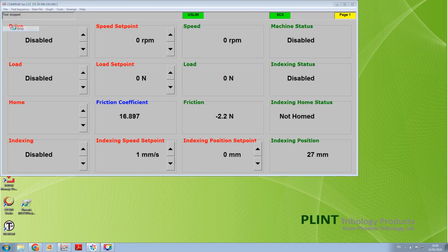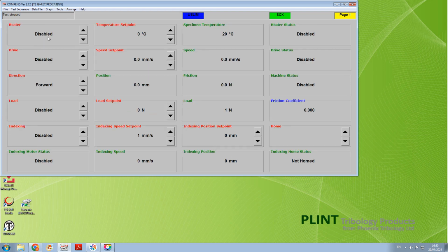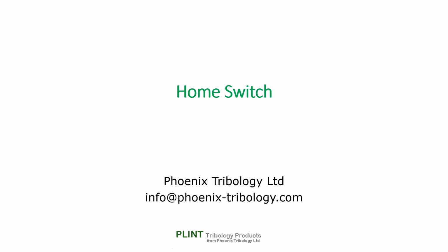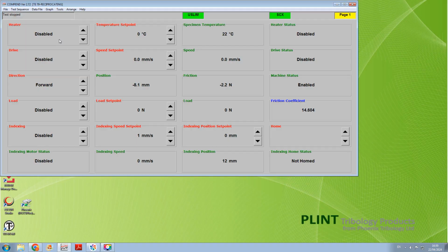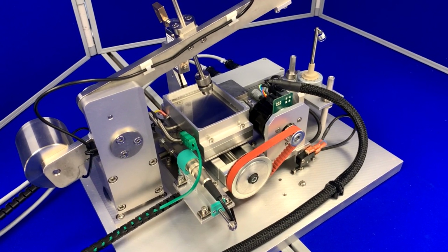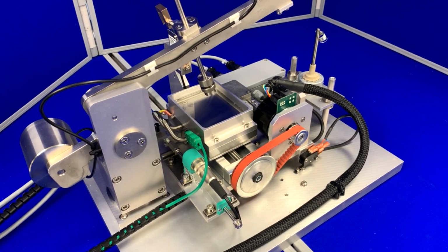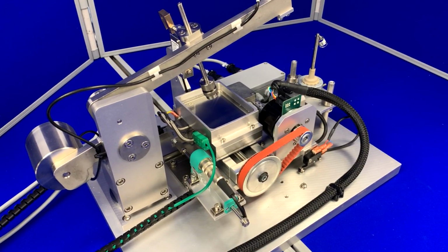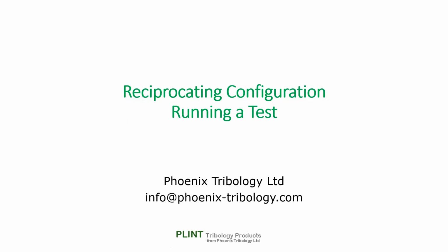From the COMPEND File menu and Load Setup, select the reciprocating test configuration. Press the up arrow next to the home box to toggle the homing action. Unlike with the pin on disc module, the reciprocating configuration can only be run using a test sequence file.